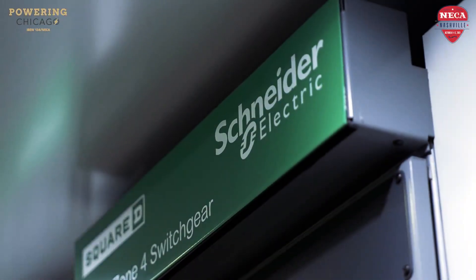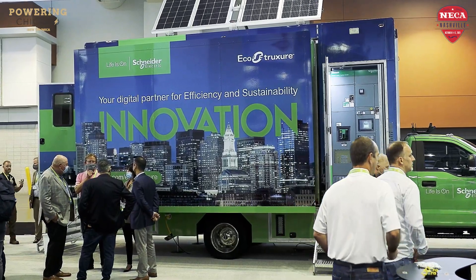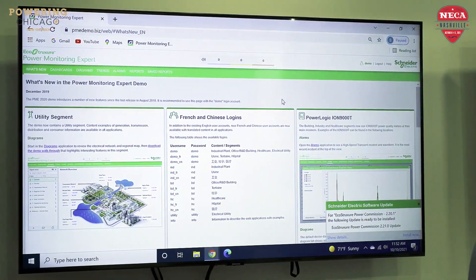So, Energy Control Center — the idea now is taking source management, which used to be ATS, automatic transfer switches in the past, and adding new sources to it: solar, PV, battery energy storage, wind, fuel cells, whatever those sources are — taking that in combination with electrical distribution together with load management.